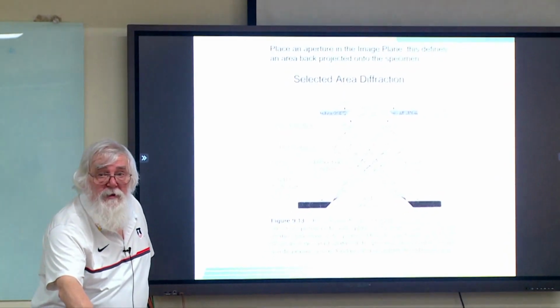The instrument you have here is not a probe corrected machine, but an image corrected machine, but you'll still be able to get a small probe. I don't know exactly which lenses you have or how small you can get, but it depends on the lens, the number of lenses, and the sizes of the apertures. But certainly 1,000 angstrom probe will be easily done on the machine here.